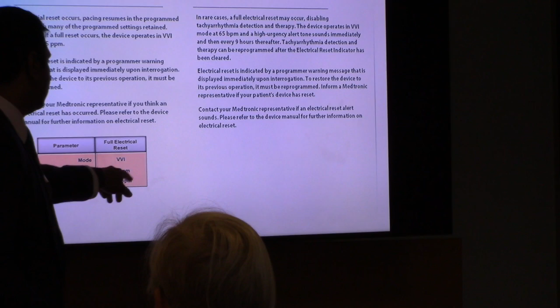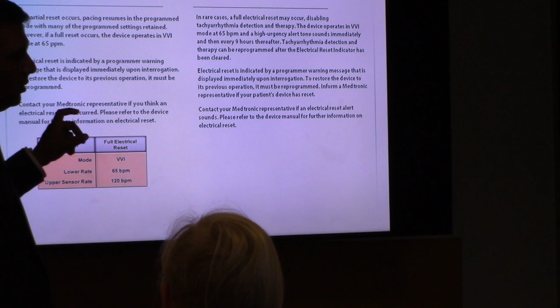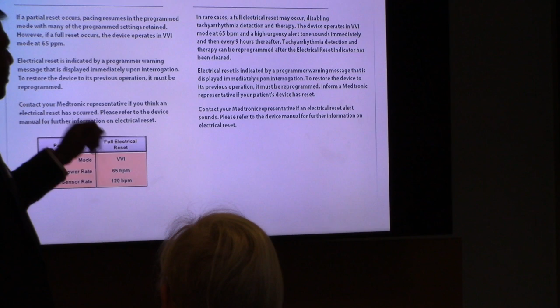And ICDs, there might be a full electrical reset that will also cause them to pace at 65 beats per minute. And you would see a high urgency tone alert in the device that will keep beeping every 9 hours. And you would have to call us and we have to reset the device to the parameters.